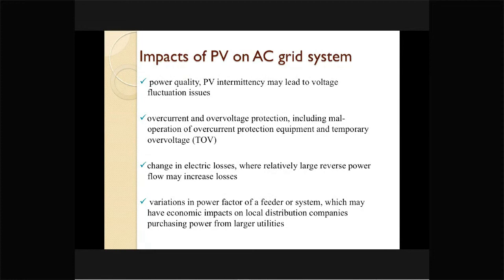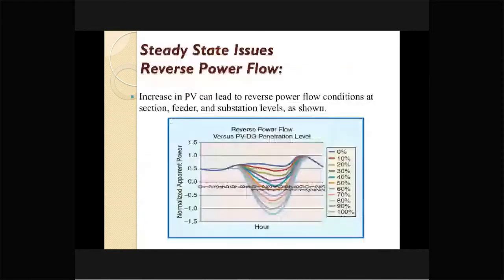Similarly, the variation of power factor is a very important factor which is seen when you go for photovoltaic integration into the grid. You can see here a representative plot to give an overview of the reverse power flow phenomenon. You can see here that at 0% loading, that means when there is no photovoltaic integration, this blue line is the power flow that is happening in the feeder.